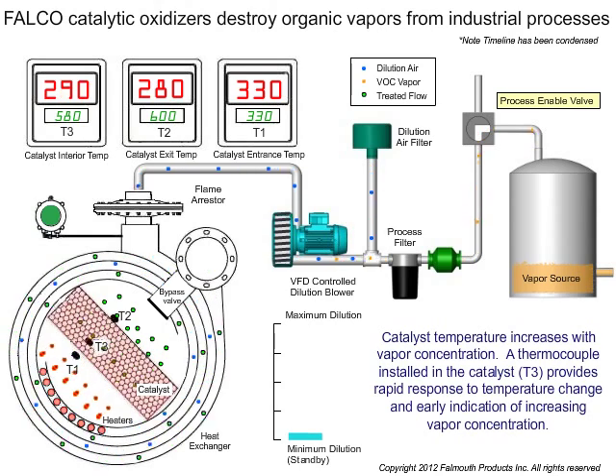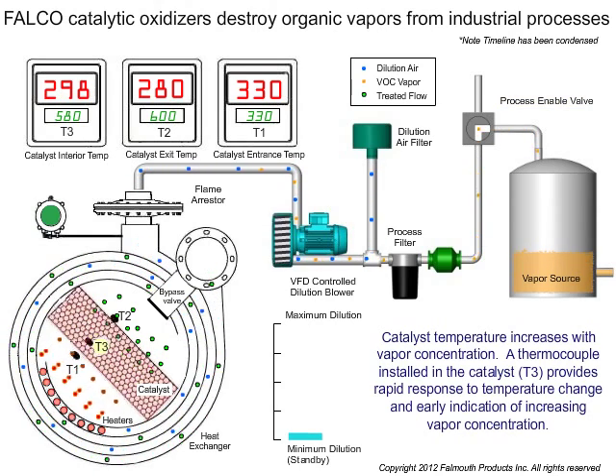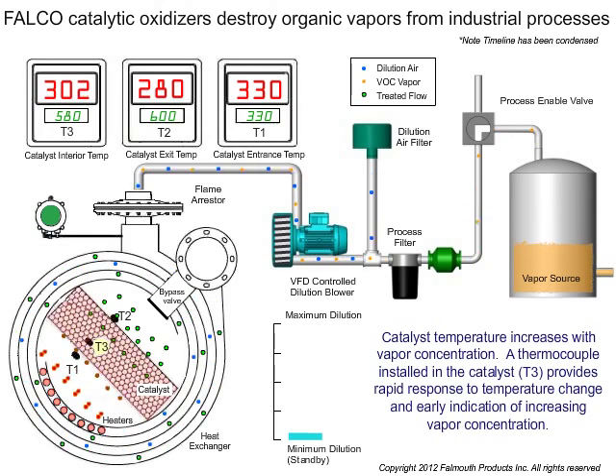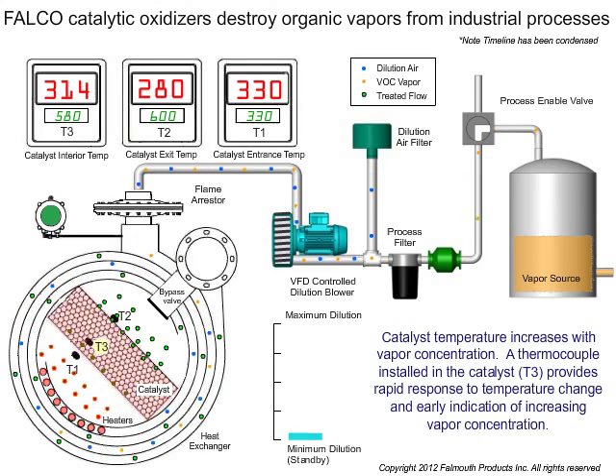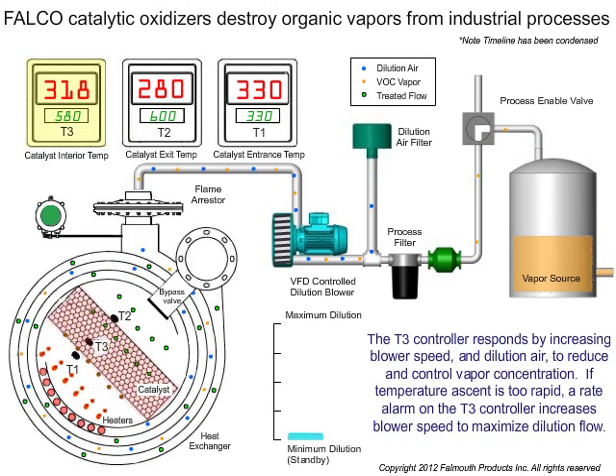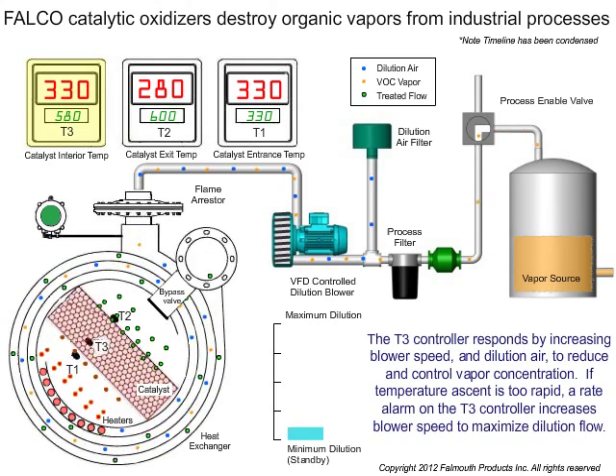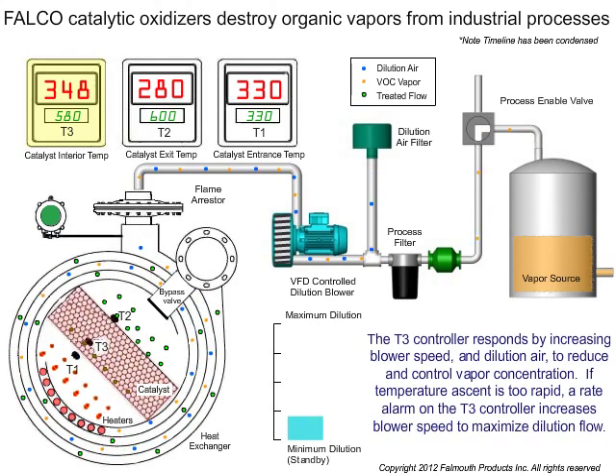A thermocouple installed in the catalyst, T3, provides rapid response to temperature change and early indication of increasing vapor concentrations. The T3 controller responds by increasing blower speed and dilution air to reduce and control vapor concentrations.